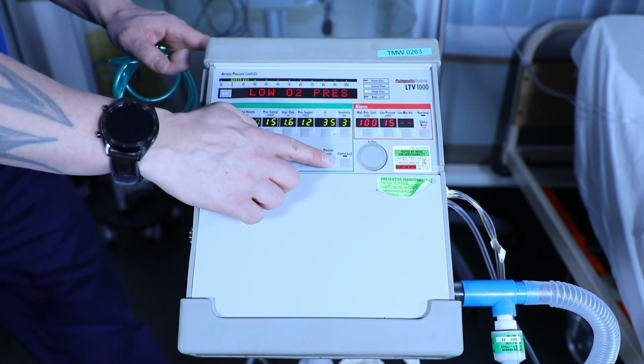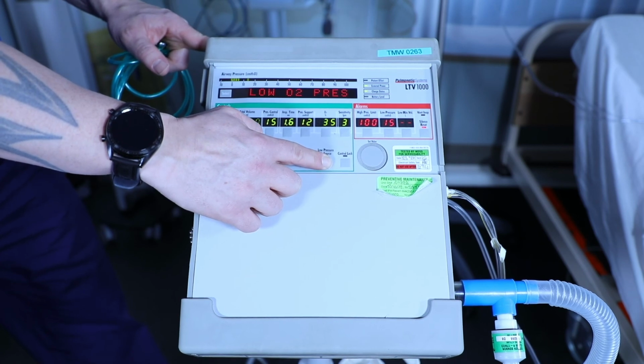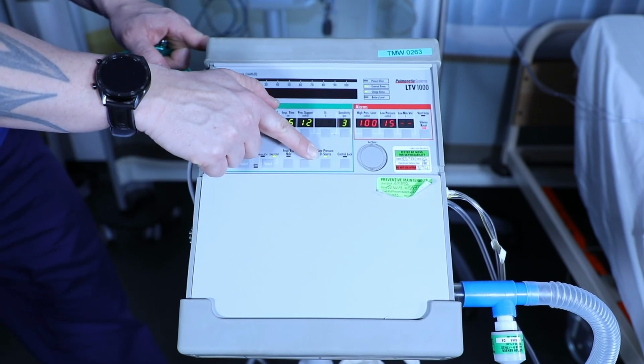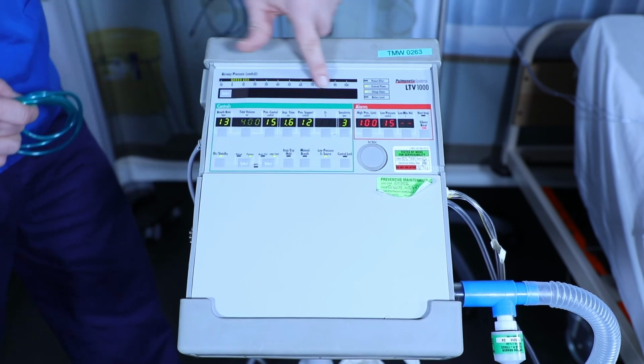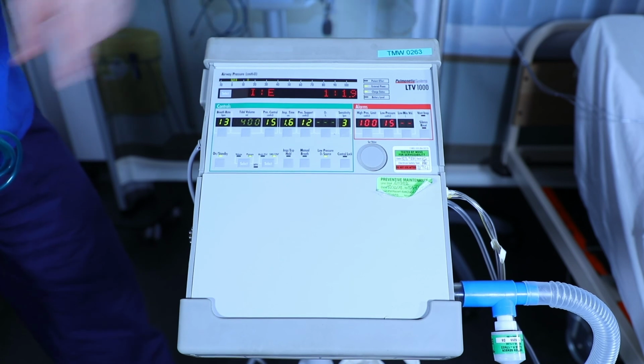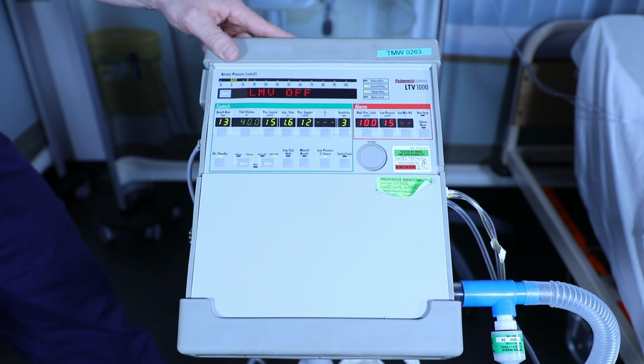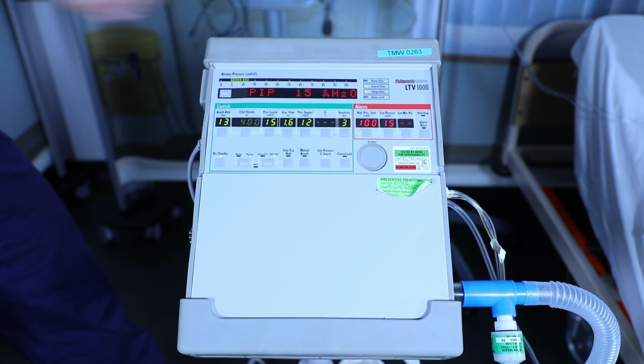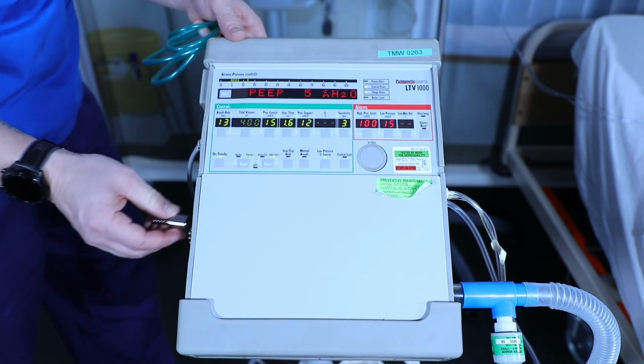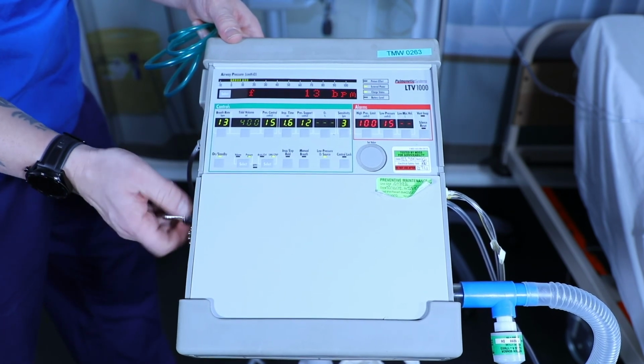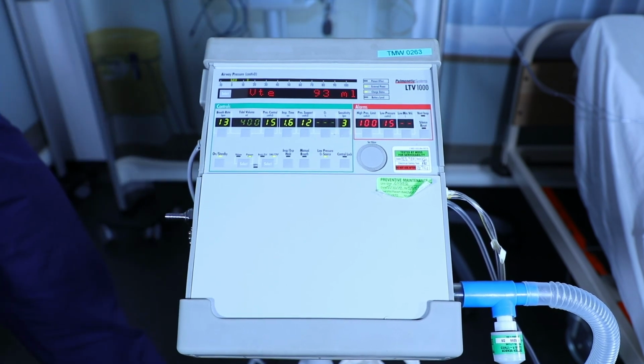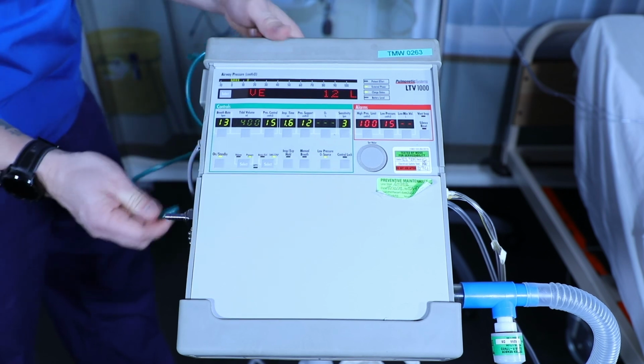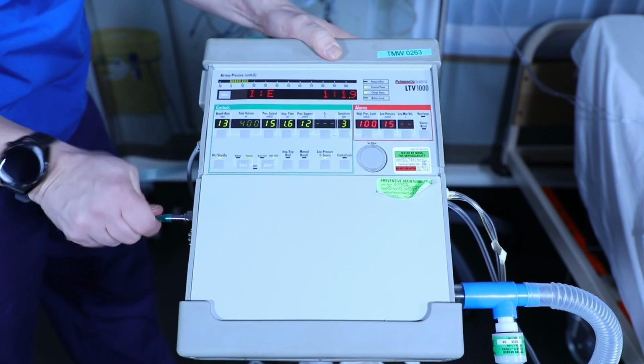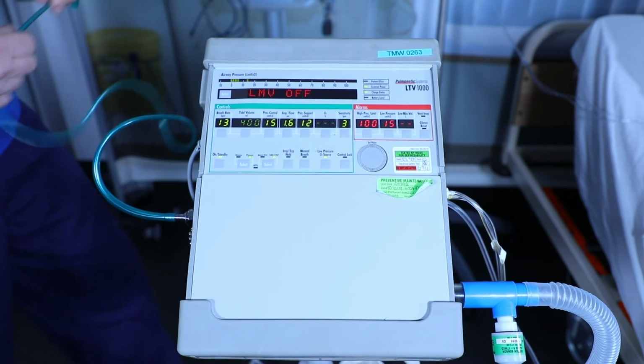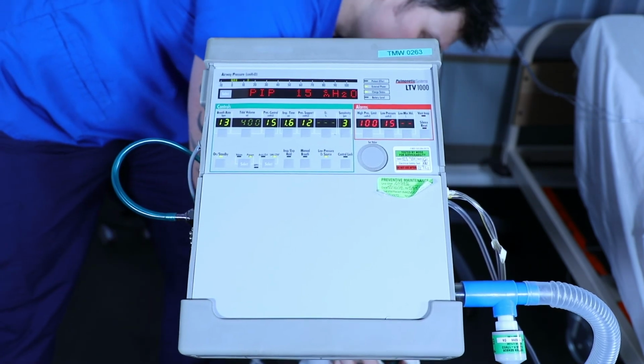Once this has been done, we can press and hold the low O2 source, and we can now see that the LED is illuminated. We can now clear the visual alarm because we're now delivering through low O2. Currently, the device would be delivering 21% room air. To be able to increase that, we connect our adapter where the high pressure O2 hose would sit. Attach the green tubing to the adapter, and then the other end connects to our oxygen cylinder.